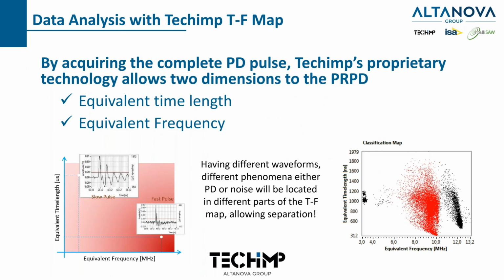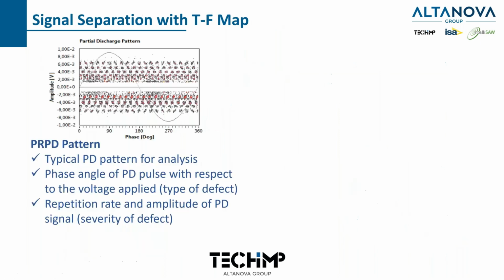So remember I said we acquire the complete PD pulse. This is why, because we're measuring time and frequency. Time being the time length of the pulse, how long that pulse is happening, and then the frequency. So why is that important? Because of this, basically. This pattern is a discharge pattern.